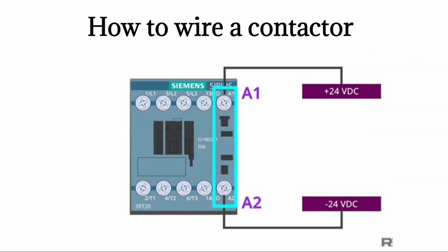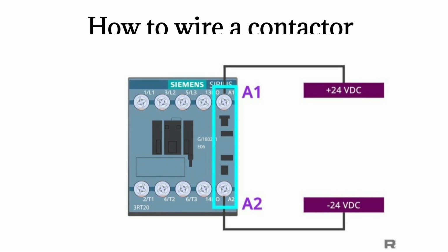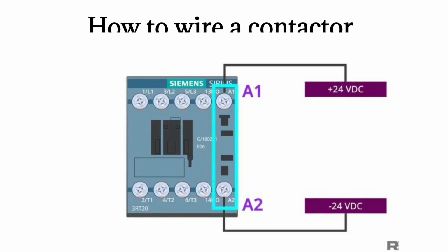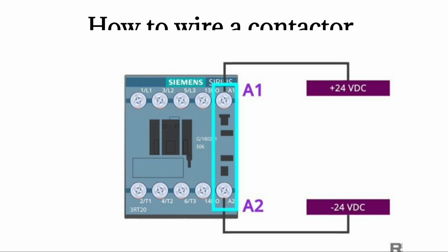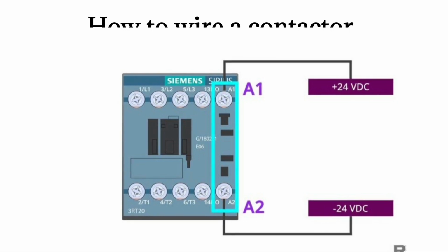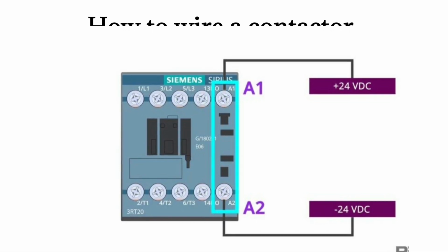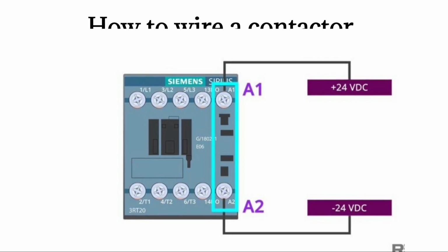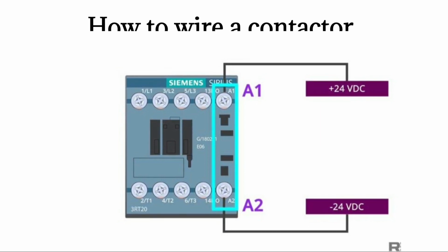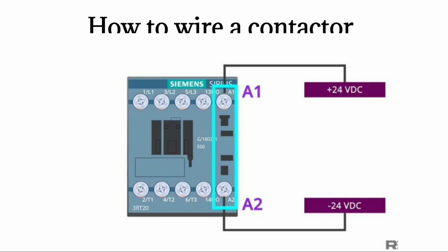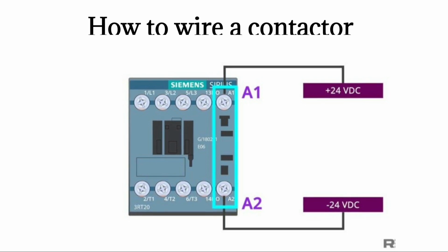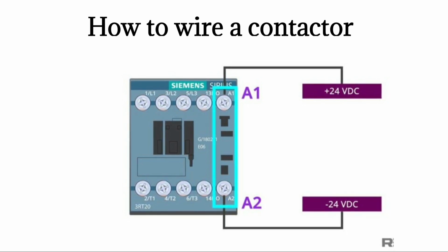How to wire a contactor now? Let's talk a bit about the wire terminals on the contactors. One, coil terminals on the front of the contactor. You'll see two wire terminals, A1 and A2. This is where we can connect a 24-volt DC power to the coil to energize it. The A1 wire terminal is where the 24-volt DC positive signal wire gets connected, and the A2 wire terminal is where the 24-volt DC negative signal wire gets connected.